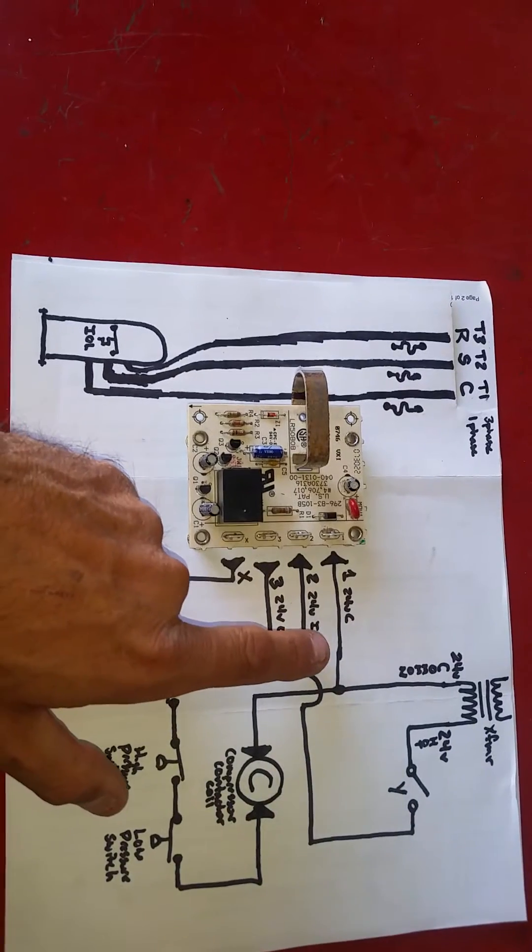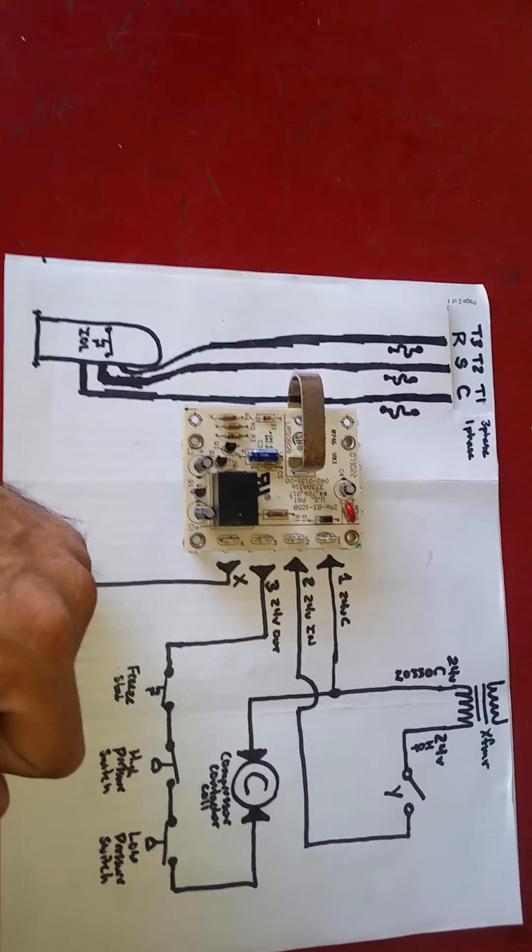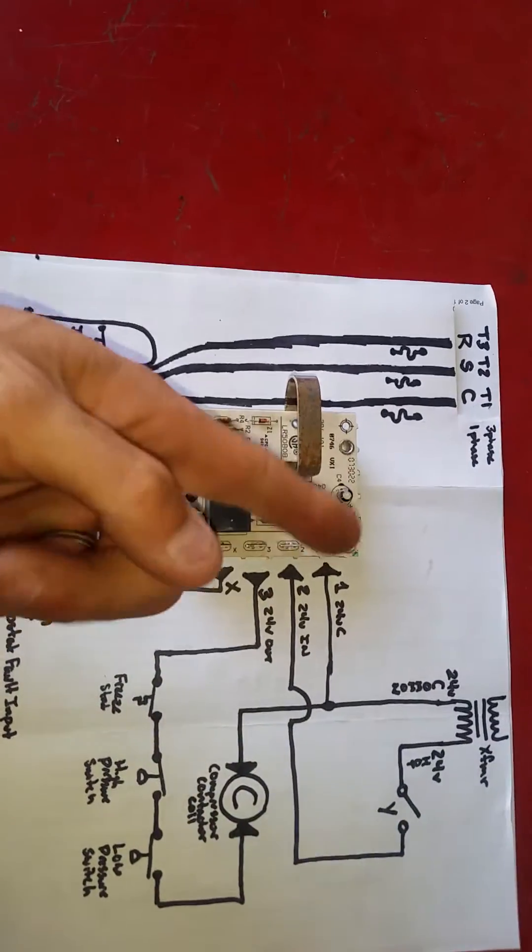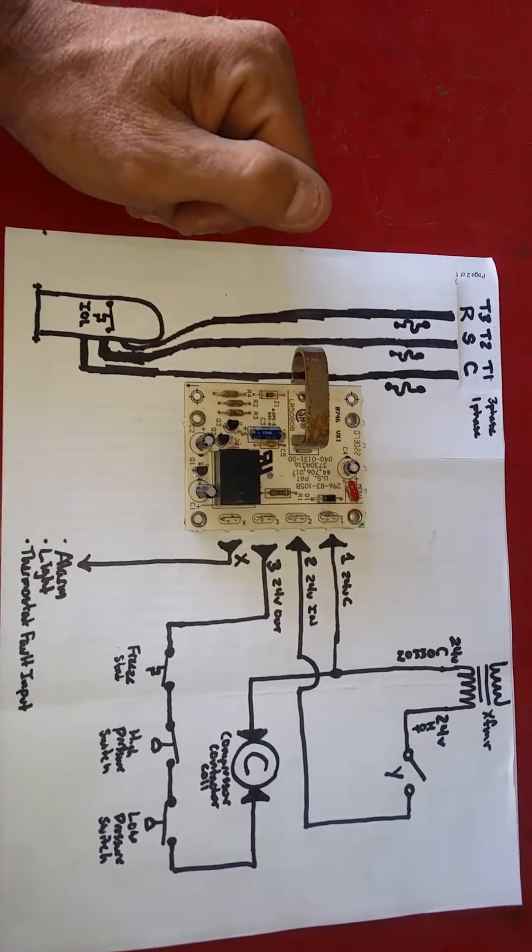And it will not reset until we discontinue 24 volts to our number two terminal. And by depowering or de-energizing number two and re-energizing it, it will reset the circuit to re-attempt another try at running. Thus, it's just a solid lockout device.